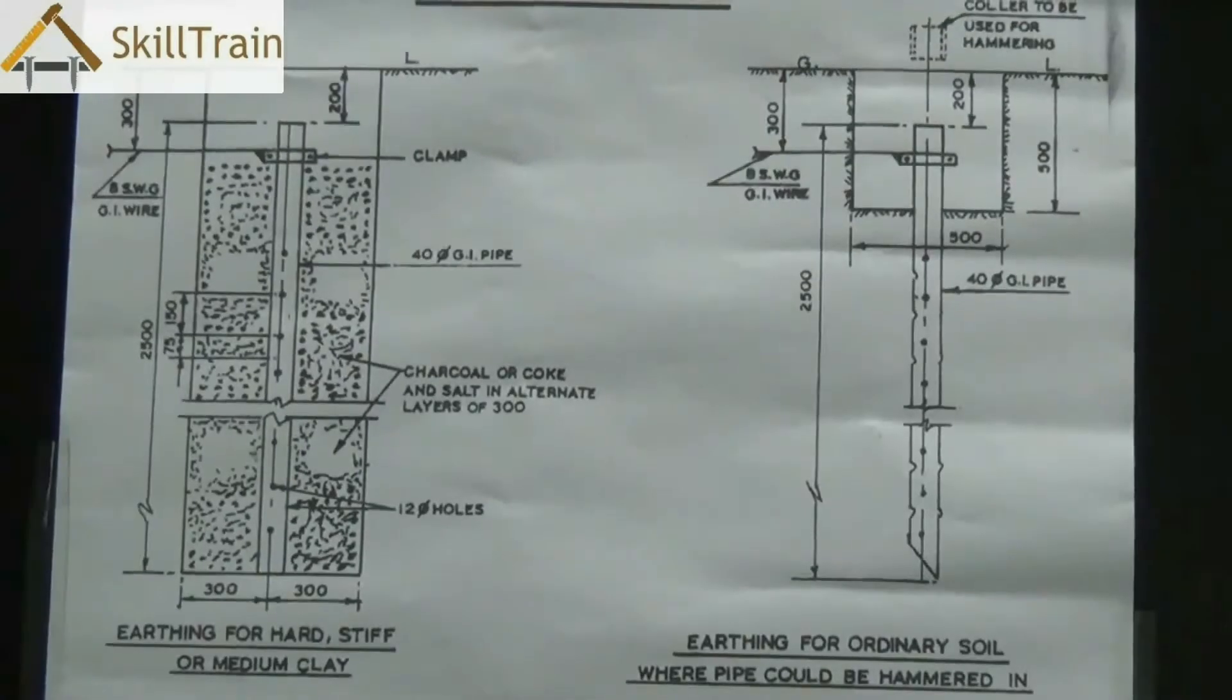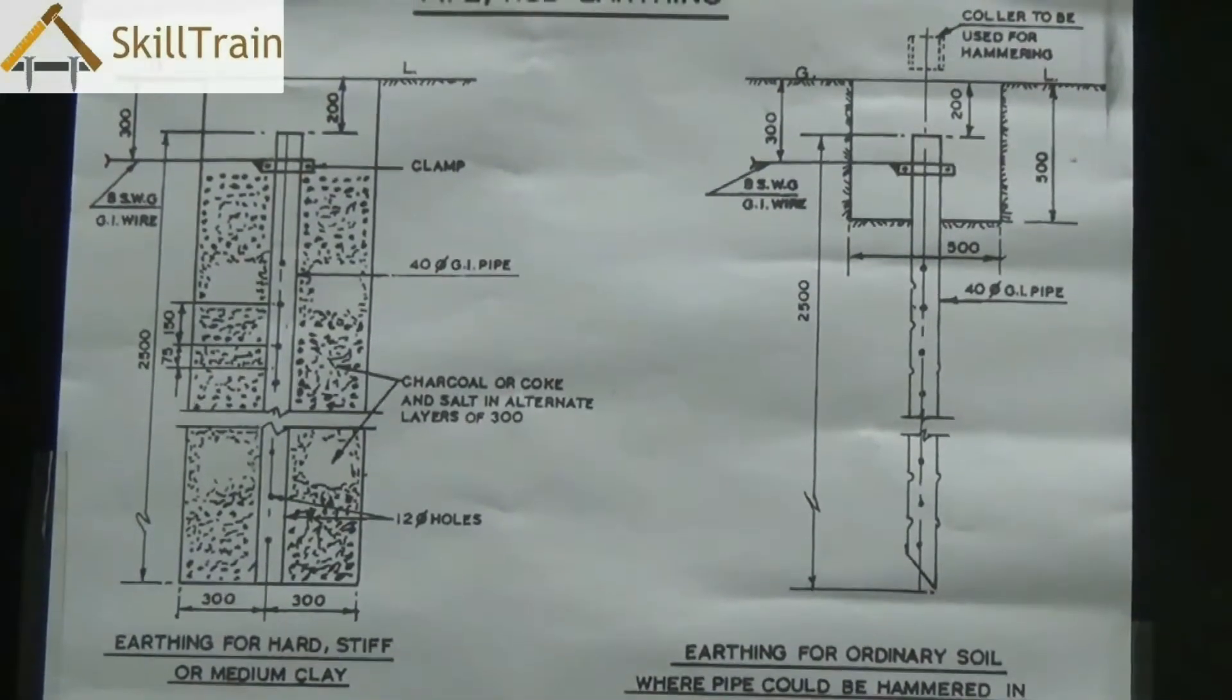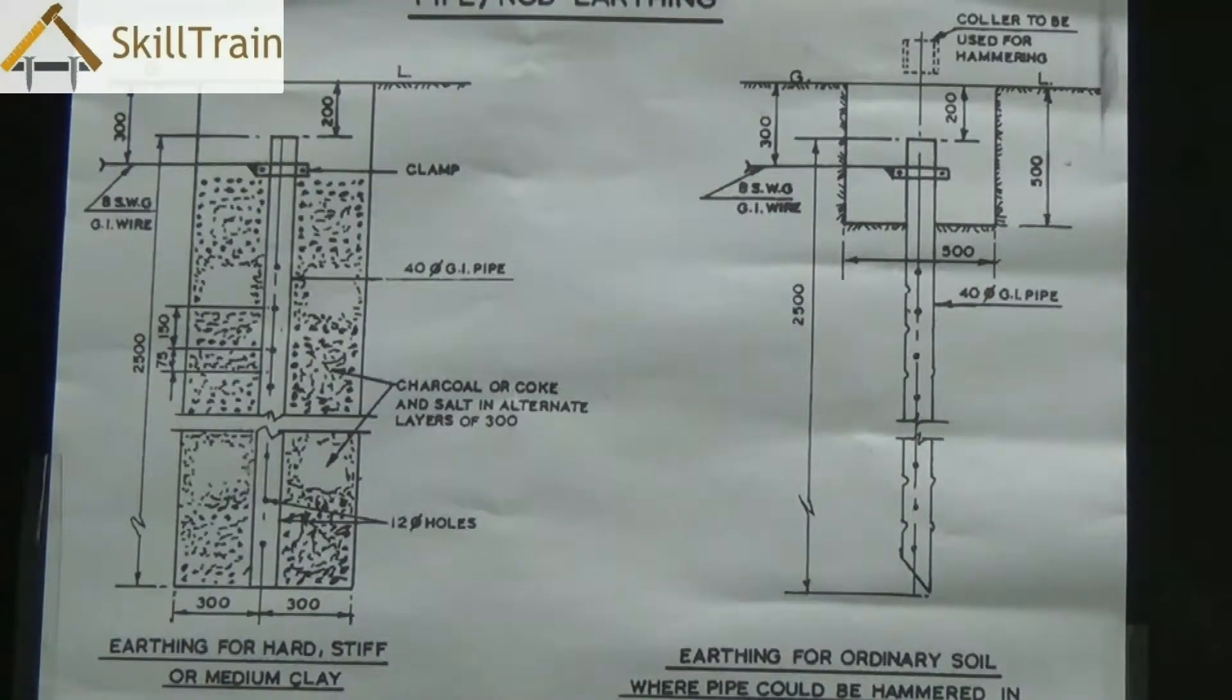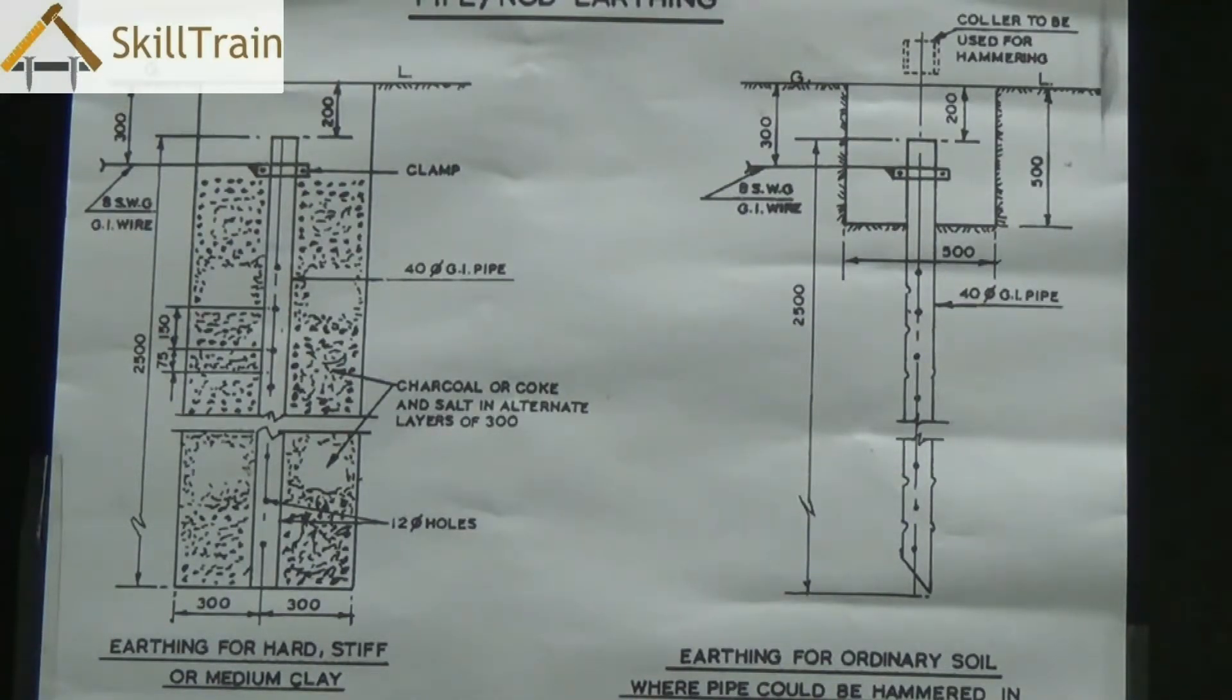Always ensure that there are holes made in these pipes at equal distances to ensure that they are properly placed and they are in full contact with the ground or with the salt and charcoal surface. The pipes we are using here are GI pipes. GI basically stands for galvanized iron pipe. The wires that are connected from the pipe to the mains are also galvanized iron wires. We did see the galvanized iron wire in one of the earlier videos when we were checking the board.